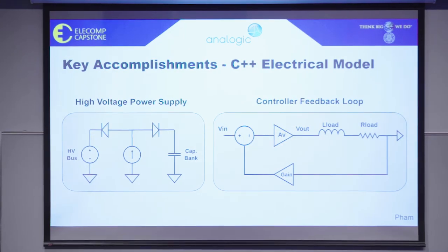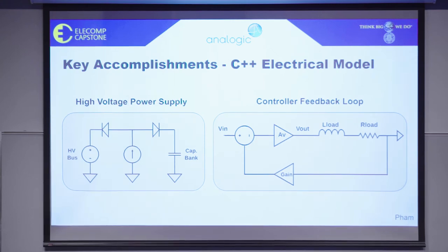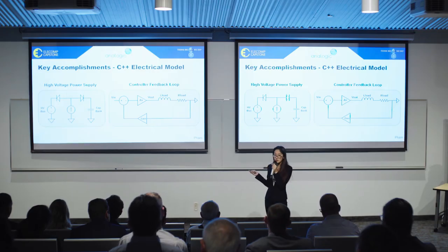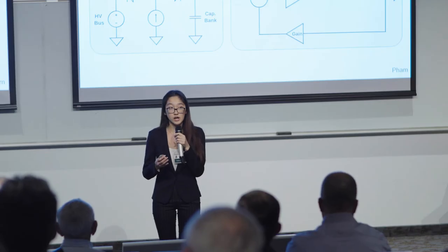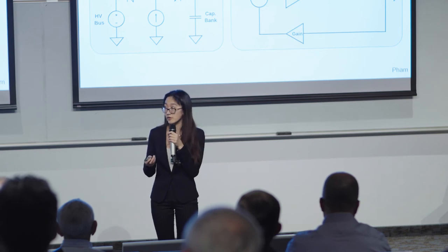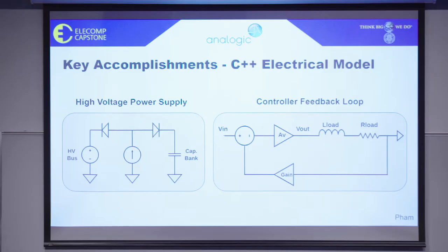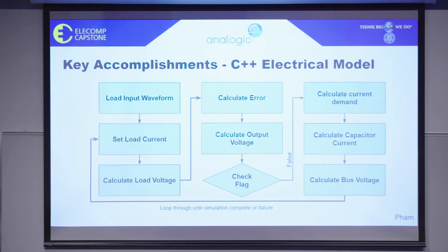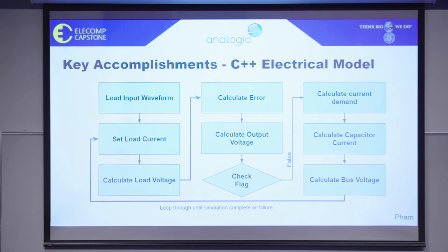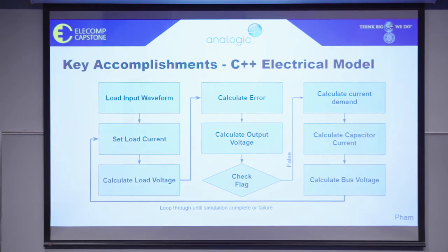The first step we took toward the anticipated best outcome was to develop the electrical model. We were given an LTSpice file which simulated aspects of the gradient amplifier such as the high-voltage power supply and the controller feedback loop. Using the LTSpice file, we derived mathematical equations describing the electrical behavior of the gradient amplifier, and then created a C++ program which is the electrical model. We chose C++ because it allows us to develop models that are efficient in runtime and processing, and it is also compile-based, which aids in the encryption aspect of the project.